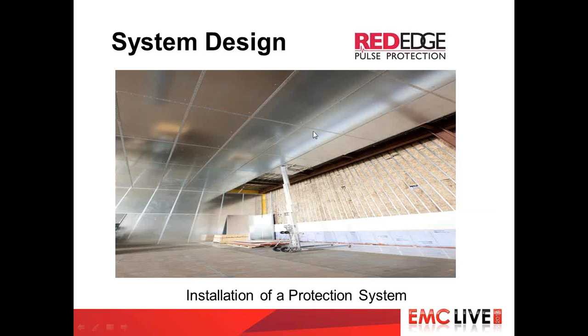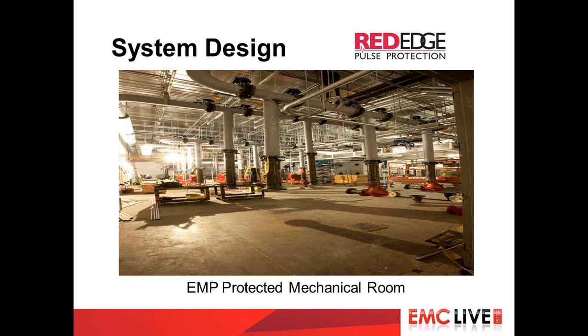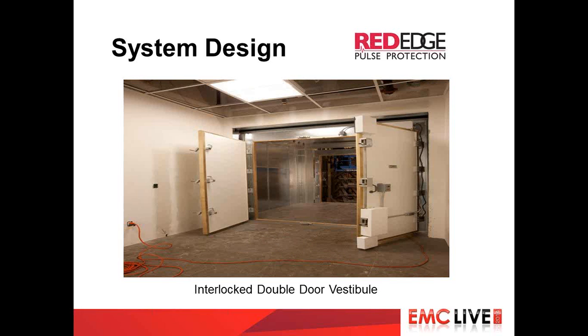In a mechanical room, you're going to get spillage, you're going to get various fluids that might wind up on the floor, you've got equipment being moved in and out, so you need something a little bit more robust on the floor than the modular shielding. Call your attention to the ceiling in this room, and in the ceiling of this room is the modular system. So the floor of this area is welded, and the walls and ceiling are modular system.